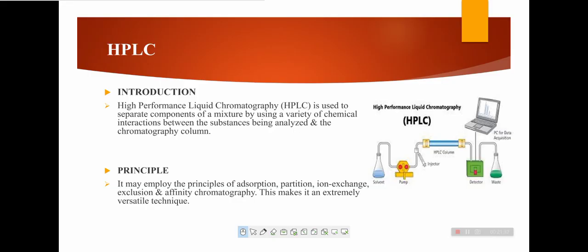The separation principle of HPLC is based on the distribution of the analyte between a mobile phase and a stationary phase. Depending upon the chemical structure of the analyte, the molecules are retarded while passing the stationary phase. The specific intermolecular interaction between the molecule of a sample and the packing material define their time on column, and thus different constituents of a sample are eluted at different times. Thereby, the separation of the sample ingredient is achieved.